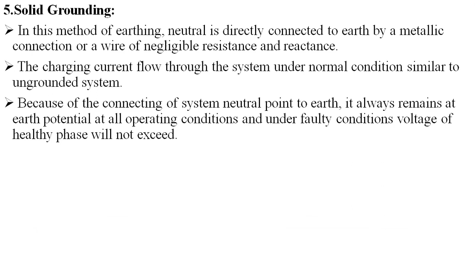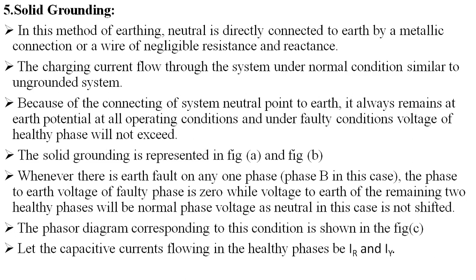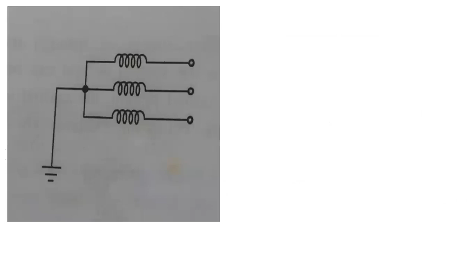So the solid grounding is represented over here, and whenever there is an earth fault on any one phase, the phase to earth voltage of the faulty phase is 0, while the voltage to earth of the remaining 2 healthy phases will be normal phase voltage, as the neutral in this case is not shifted. The phasor diagram is also shown here, and the capacitive currents flowing in the healthy phases are IR and IY. These are the corresponding pictures for that.